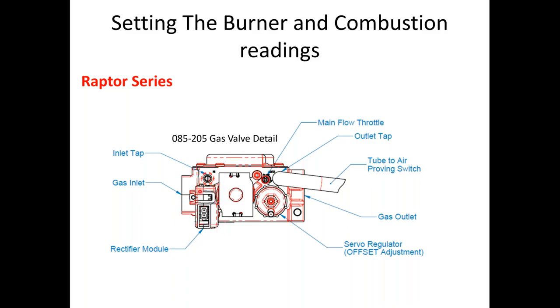And on the rectifier module, on the side right here where the laser pointer is, there's a wonderful little switch there. And that switch can often be turned in the off position if we're checking our inlet gas pressure. We've got to take our hoses back off. We'll bump that switch in the off position and it'll give you the belief that the gas valve is defective. The gas valve, you'll test here, you'll get 24 volts going to it and the gas valve will not open. That switch needs to be in the I position, not in the O position.